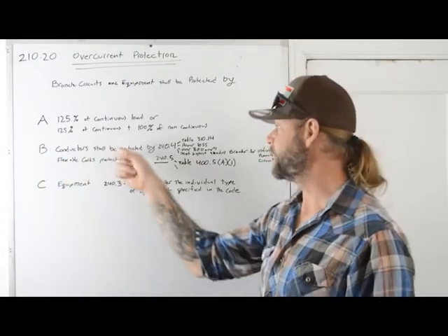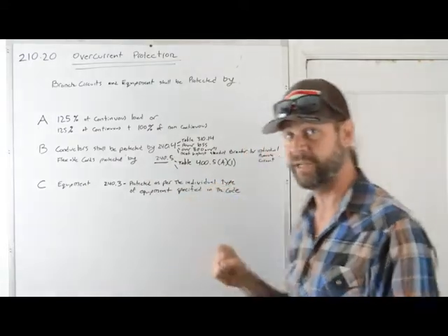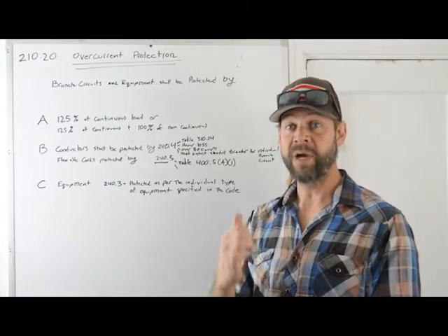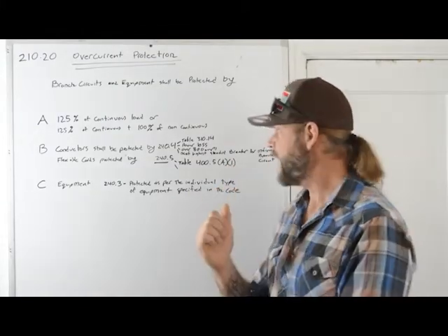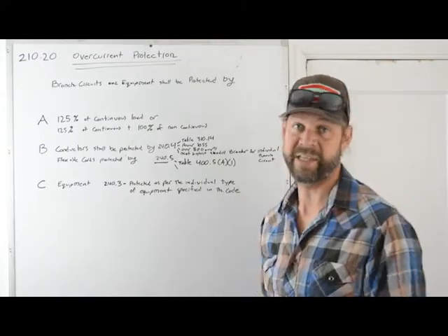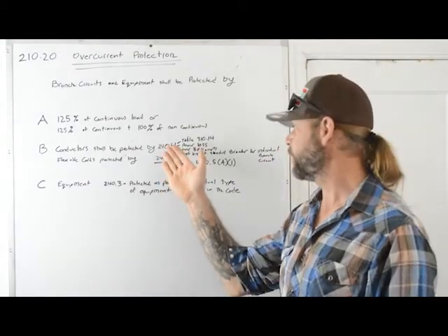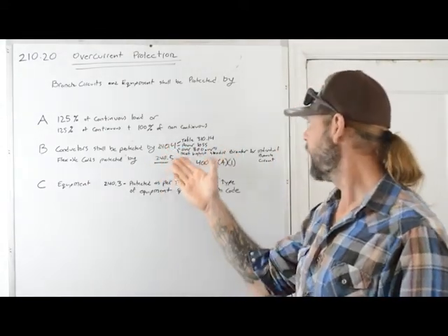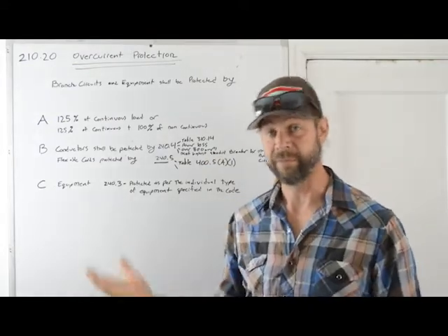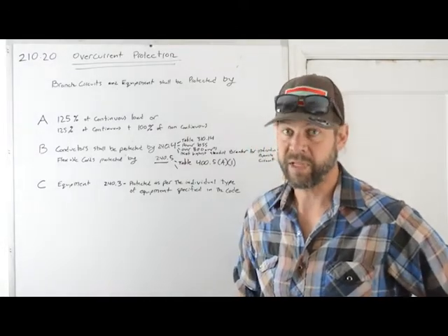Conductors. Conductors shall be protected by, and it just references 240.4, which is a big code section that we'll get to, but it says essentially you will protect your branch circuits according to Table 310.14, which is an ampacity table for conductors, or there are exceptions for power loss, things over 800 amps, and the next highest standard breaker for individual branch circuits for individual equipment, right? And you'll see those exceptions in other code sections.